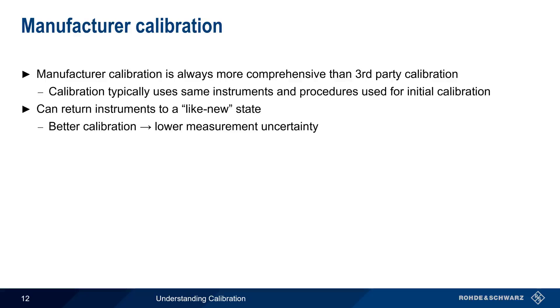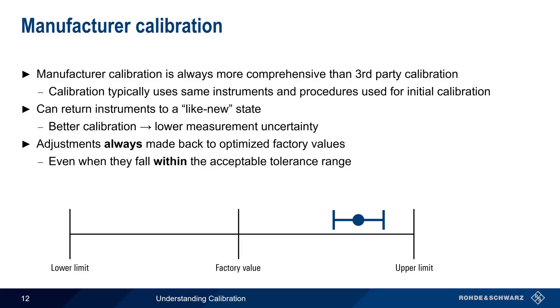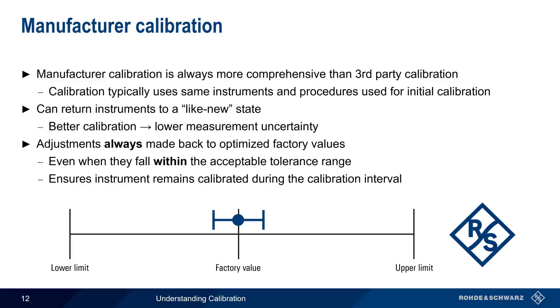Note, too, that in a manufacturer calibration, adjustments are always made to ensure that all parameters are at the optimized factory values. Even values that fall within the limits and are passing are still adjusted back to the original factory value. In addition to improving measurement uncertainty, these adjustments also help to ensure the validity of the manufacturer-recommended calibration interval — that is, instruments remain calibrated longer when values have been readjusted to the original factory values.